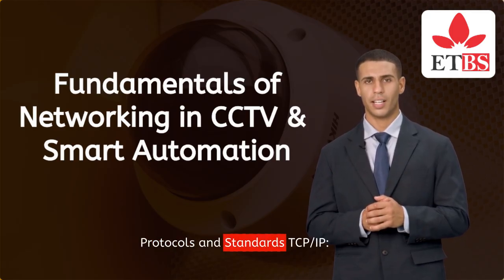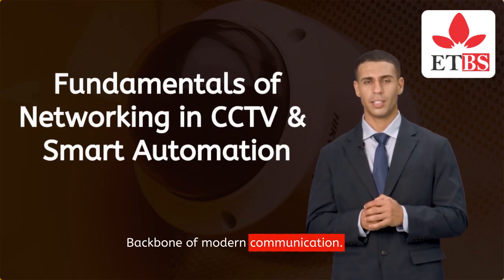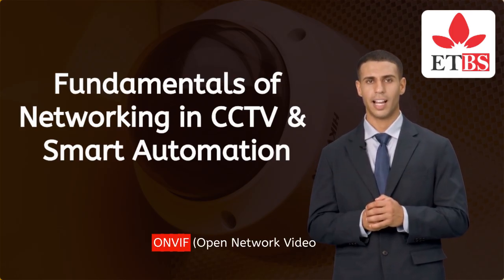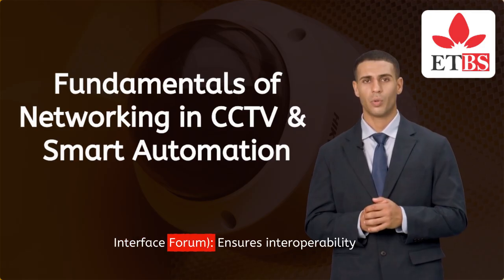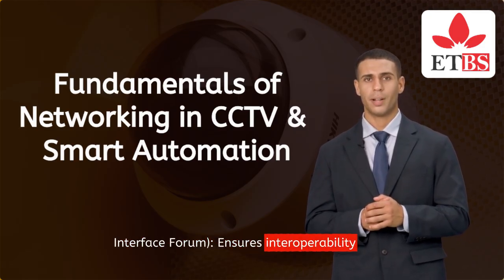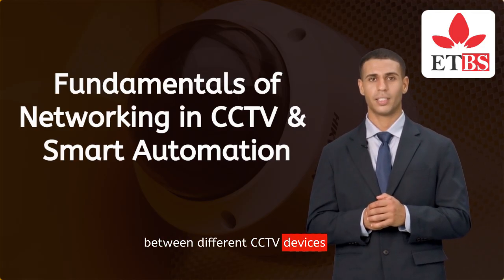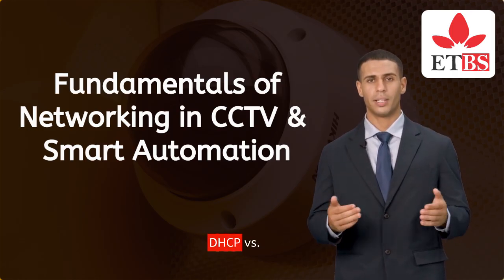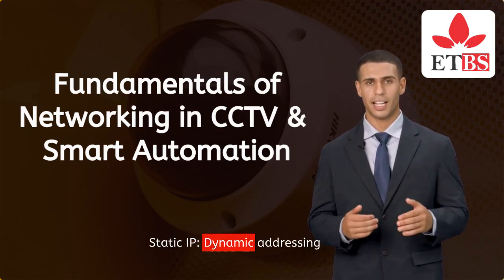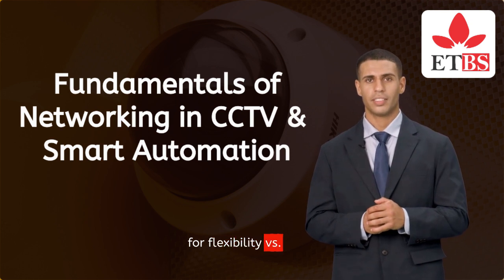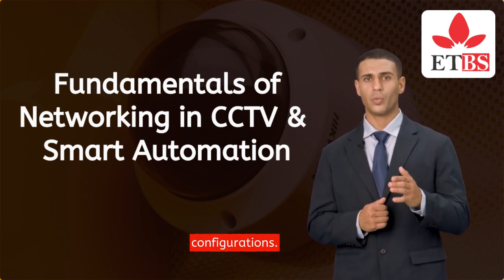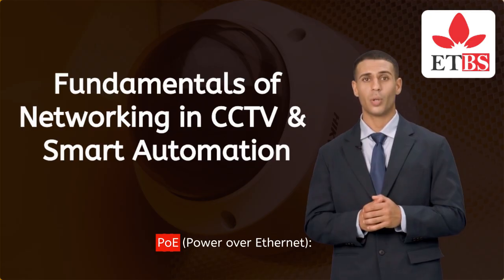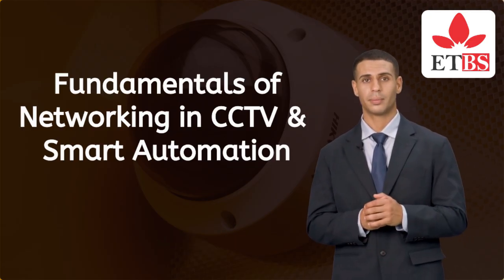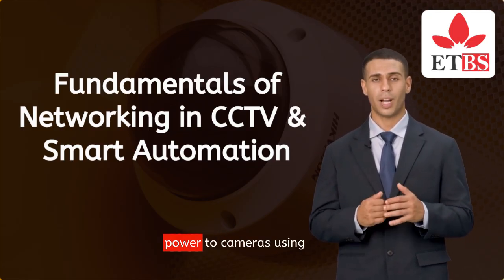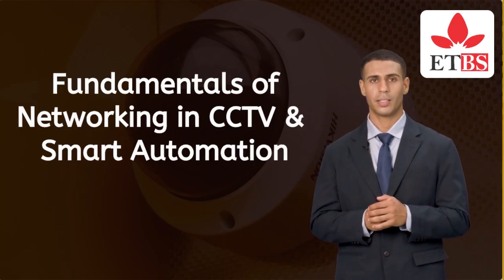Protocols and standards. TCP/IP. Backbone of modern communication. ONVIF, Open Network Video Interface Forum, ensures interoperability between different CCTV devices and brands. DHCP versus static IP, dynamic addressing for flexibility versus static for stable CCTV configurations. PoE, Power over Ethernet, supplies both data and power to cameras using a single cable.